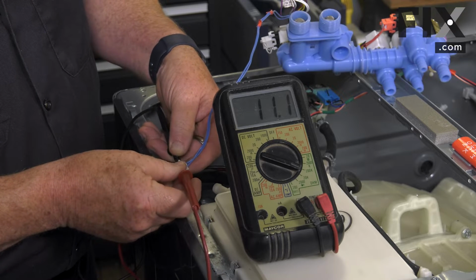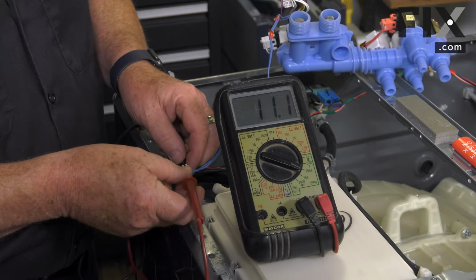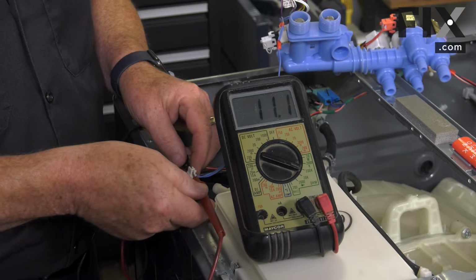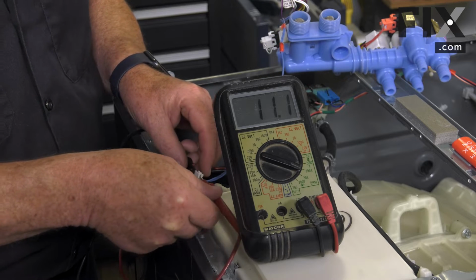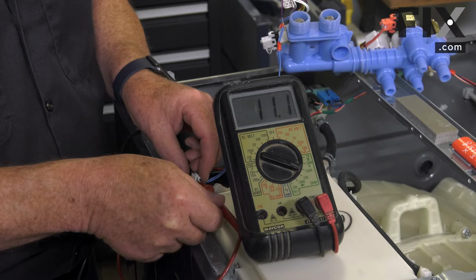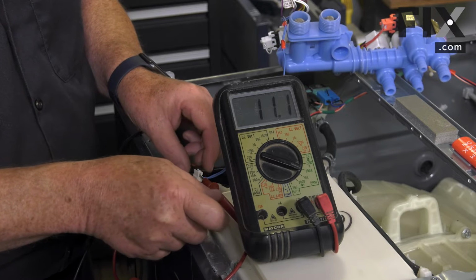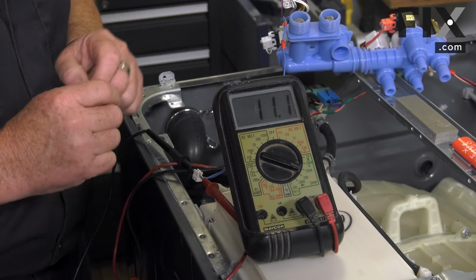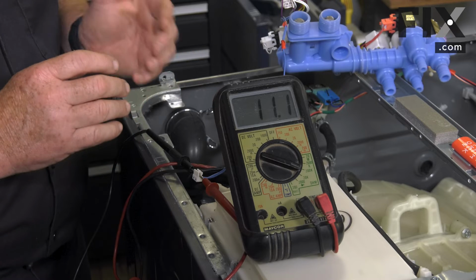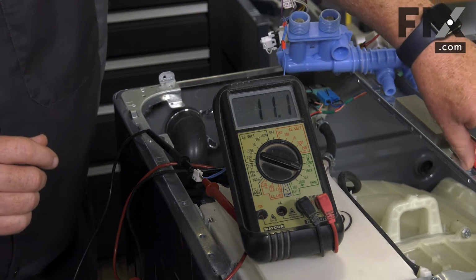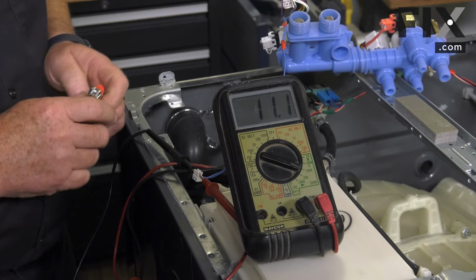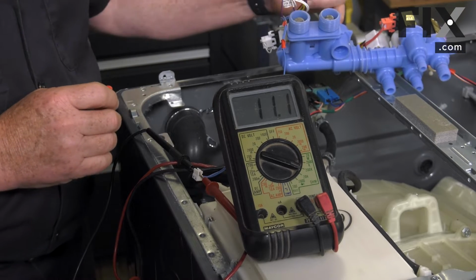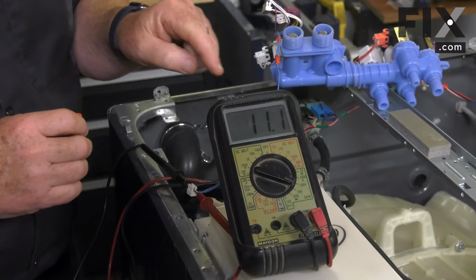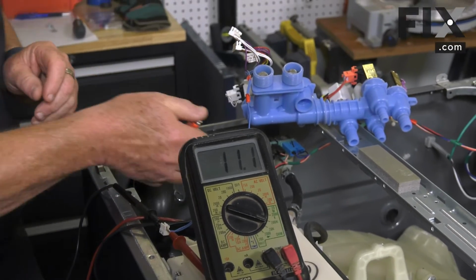So with my meter, you can see we have a reading. Typically, thermistors at room temperature read about 1,000 ohms. So we're not far off. If you don't get any reading at all in doing this, then you know that temperature sensor is bad. But if you want to see the effect and how it works, I'm just going to, for example purposes, apply a little bit of heat to the area where that temperature sensor is, and you should see this reading change once it's being warmed up.